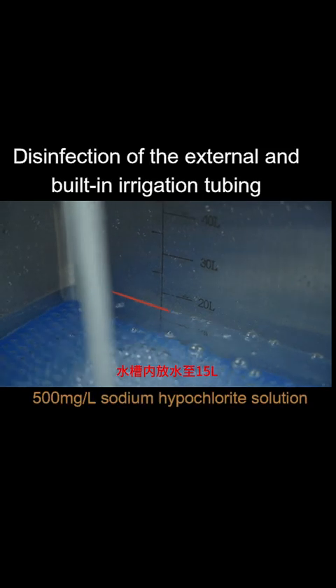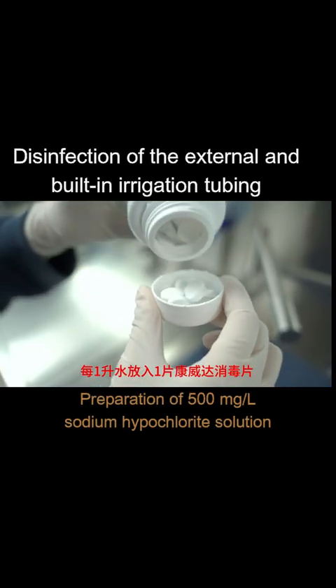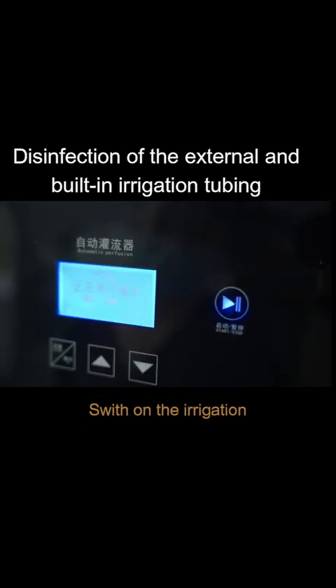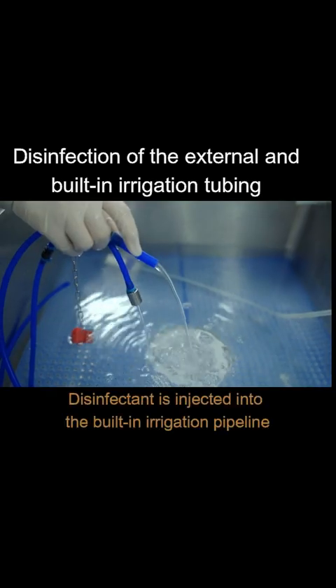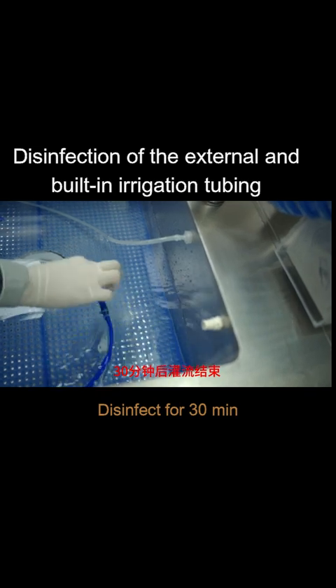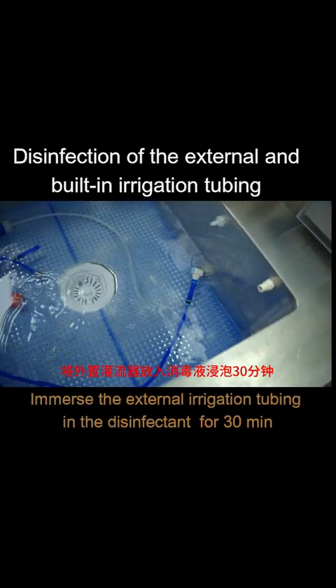The targeted improvement measures, changing the built-in irrigation tubing, including the circulating irrigation pump, and the daily disinfection of the circulating built-in irrigation tubing at the end of the day's work, significantly reduced the disinfection failure. After implementation of these preventive measures, the qualification rate of disinfection increased to 100%, and the detection rate of Burkholderia cepacia decreased to 0.